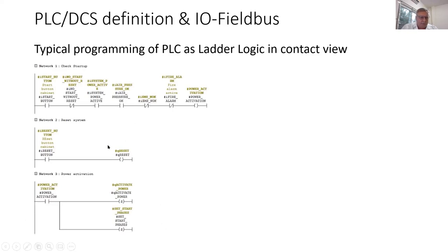So these are some typical programming styles where we came from. When you remember, in the beginning, we always had ladder logic. And this is how they started to develop programming with the early PLCs, in these structures. Each of these symbols indicates just a contact. This is a contact which, when it is active, closes, and this one, when it is active, opens. Then you see that if everything is on, then your actor will start. So this is the target that you want to control.